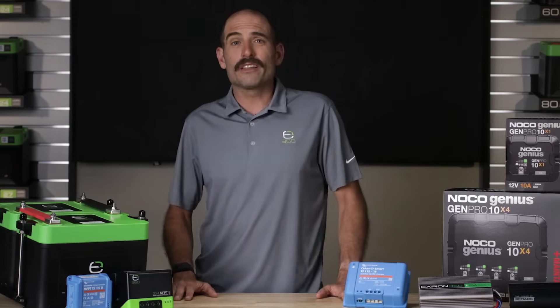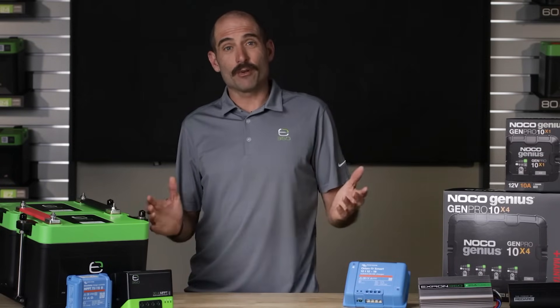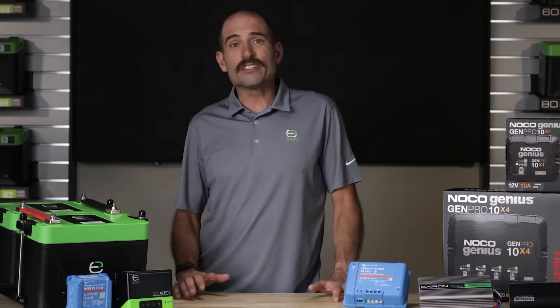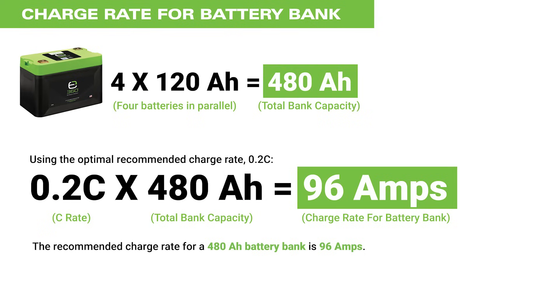To properly apply these guidelines, you will need to establish a C rate for the actual battery or battery bank that you are using. For a single battery, you can use the C ratios directly. If you have a battery bank, you will need to calculate its effective capacity. For example, a string of 4 120 amp hour batteries configured in parallel would have an effective capacity of 480 amp hours. If you want to charge at a 0.2C rate, you will need to charge at 96 amps.